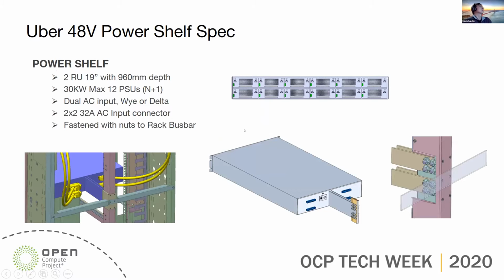This is the key spec for the Uber power shelf. The power shelf is 2 RU high with 960 millimeter depth, counted from the front panel of the power shelf to the edge of the bus bar. The maximum power is 30 kilowatts, designed with 12 power supply slots. In this configuration, we can do either 11+1, 8+1, 5+1, or 2+1 to keep three-phase balance and to accommodate the different power requirements at the rack level.